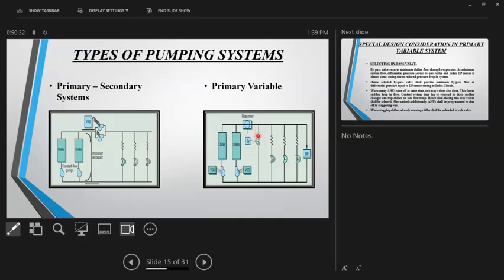So minimum flow through this valve, what is it? You should select a valve. Let's say, for example, your differential pressure setting is 1 bar, and your minimum flow through this is 40 GPM. You should go to the valve manufacturer and say, give me a valve with 40 GPM, and at 40 GPM it should have 1 bar pressure drop. If you could do that, then that valve is likely to give you a good, smoother control.